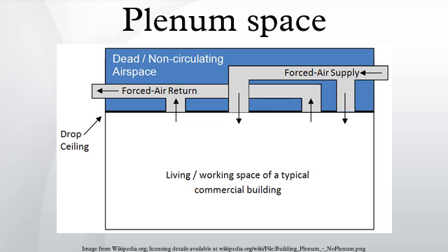The cavity plenum space is typically used to house the communication cables for the building's computer and telephone network. However, it has been proposed that the growing abandonment of cable in plenum spaces may pose a serious hazard in the event of a fire, as once the fire reaches the plenum space the air flow present supplies fresh oxygen to the flame and makes it grow much stronger than it would have otherwise been.